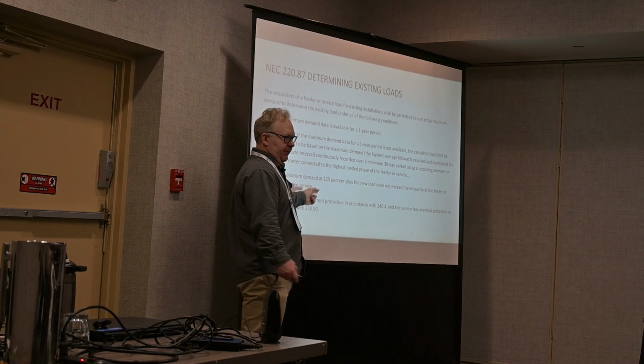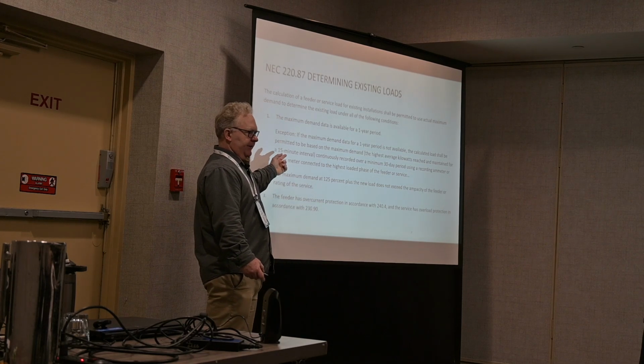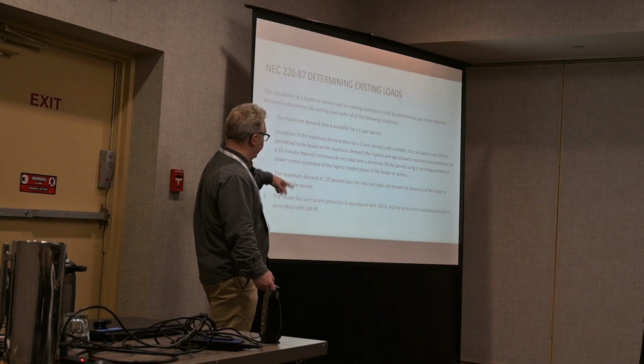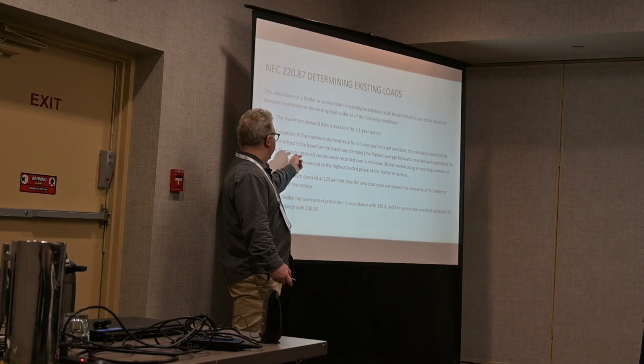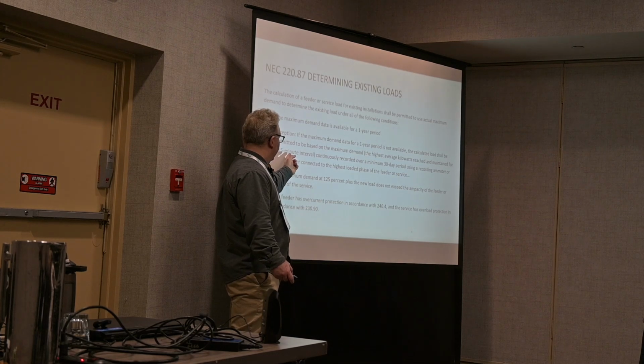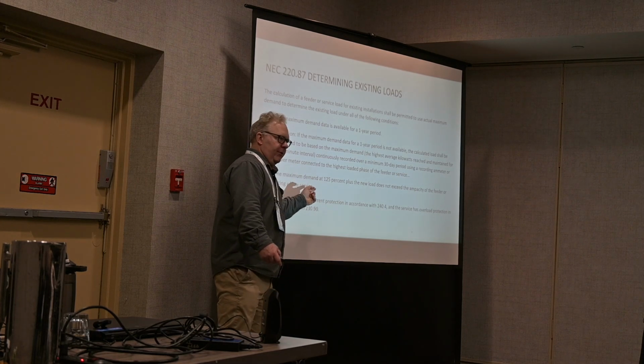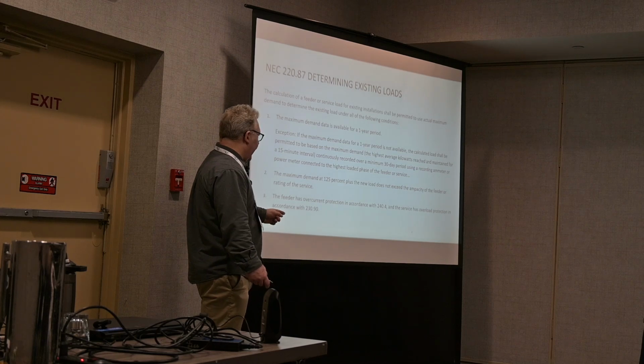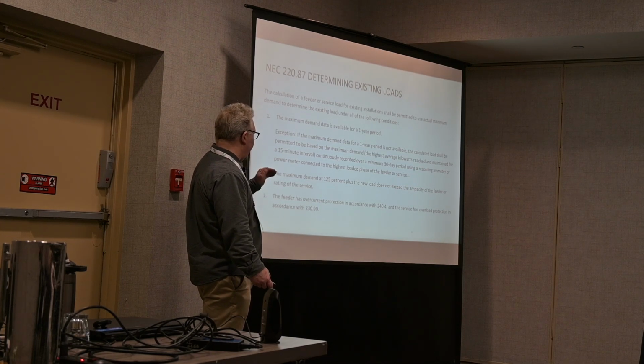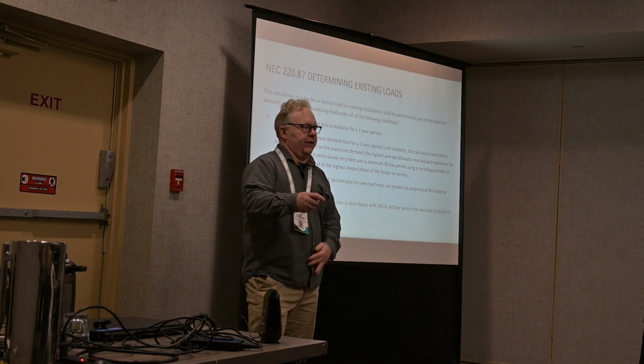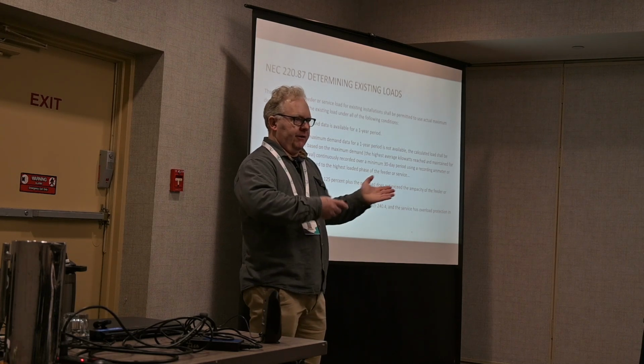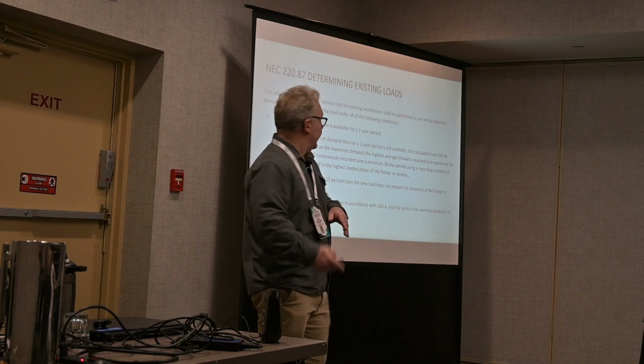And then you have to add in a safety factor. It's a 25% safety factor. And I'll take you through this in a little more detail in the next slide. But once you have that data, you add in an extra 25%. And then you add in the additional loads that you're thinking about adding. And if that's still under the panel service rating, then you're good to go.